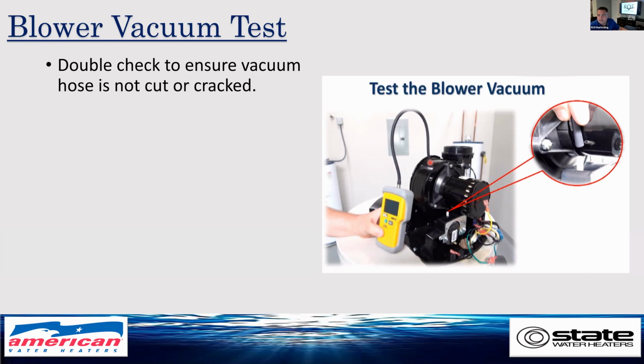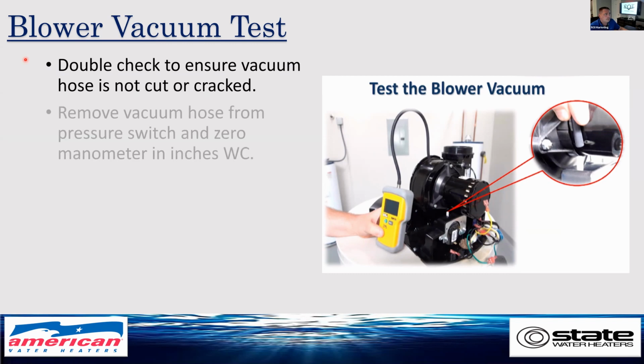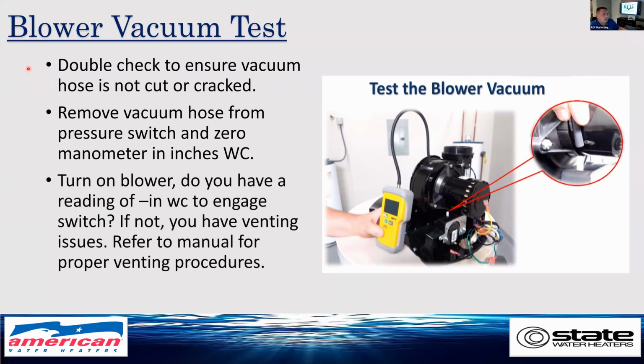So you know that brass connection is not replaceable as a part, so the entire blower has to be changed. So remove the vacuum hose from the pressure switch and zero your manometer to inches water column. Turn on the blower, and do you have a reading of negative inches water column to engage the switch? If not, you more than likely have a venting issue, and you refer to your manual for proper venting procedures for that particular unit.